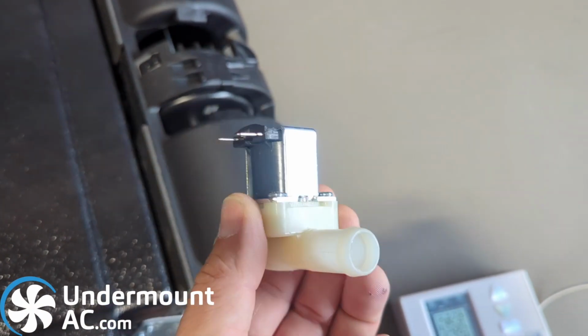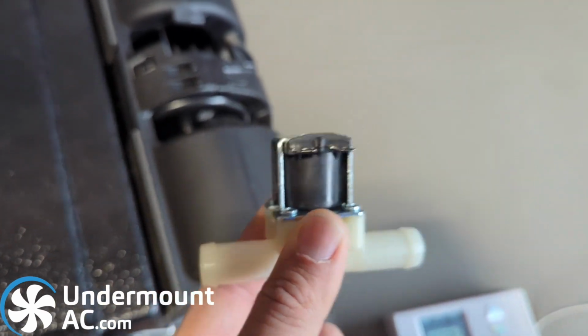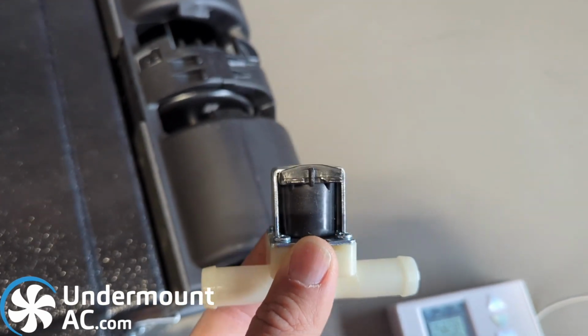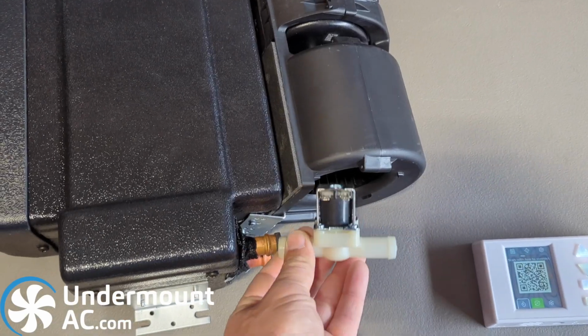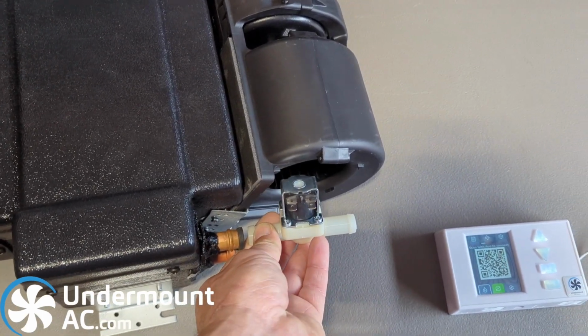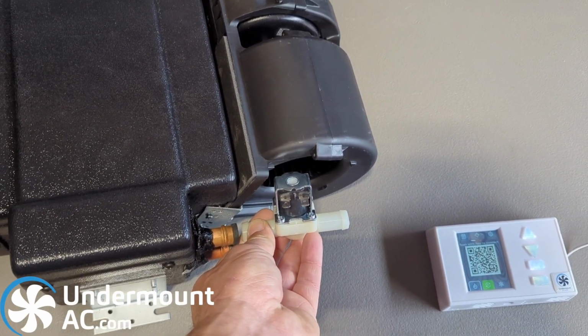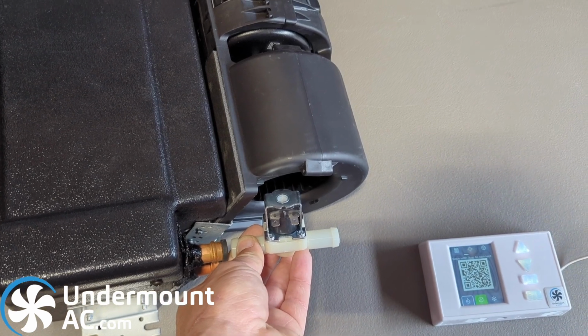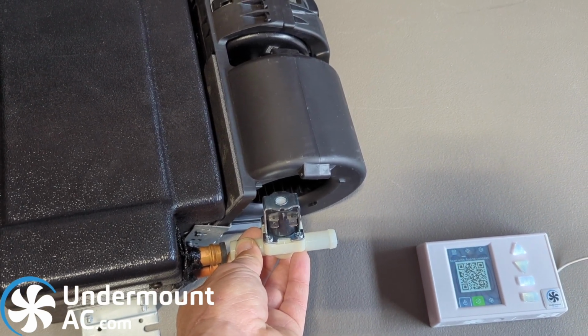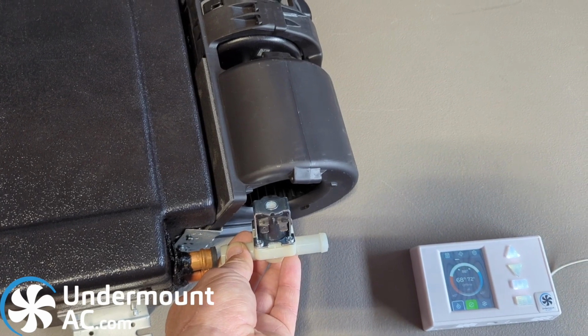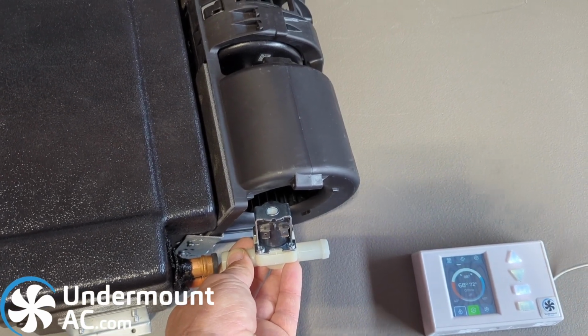This is a 5/8" port, normally closed solenoid. This solenoid would be on the input side and would be normally closed, not allowing any water to enter the evaporator unless the thermostat calls for heat, which would stop your AC system from running, and it would take over in heat mode.